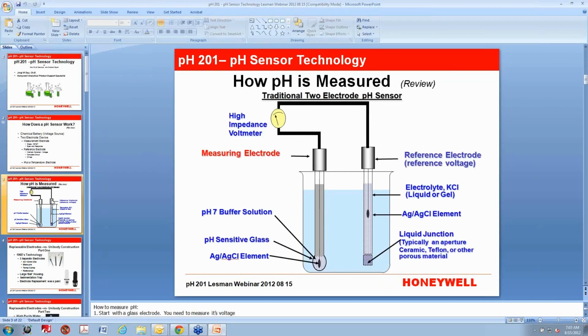Okay. So this is just a quick picture of what a pH sensor looks like and how it works. You have your pH-sensitive glass on the measured side. You have a silver chloride wire, and then you have a buffered pH 7 solution inside the glass. So when you put this glass into your fluid, if you're at 7 pH, it will generate 0 millivolts across the glass because it's 7 pH inside, 7 pH on the outside. If you put it in a 6 pH solution, it will generate 59.15 millivolts. In a 5 pH solution, 118 millivolts, etc. So it's 59.15 millivolts per pH unit.